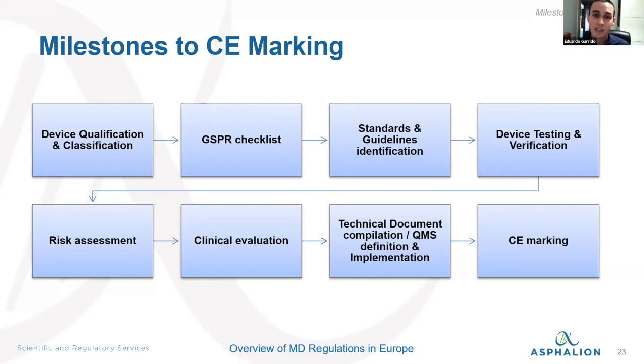Then once you have classified your device, you've got to go to Annex 1 of the Medical Device Regulation and identify which requirements are applicable to your device. Then you have to demonstrate compliance with these requirements using standards and guidelines. This should be followed by the testing of your device following the standards you have identified as applicable to your device. You will have to perform a risk assessment and the clinical evaluation.